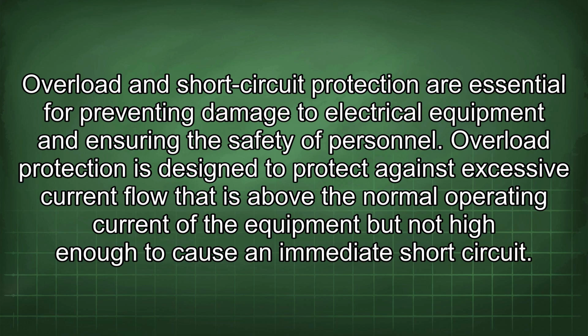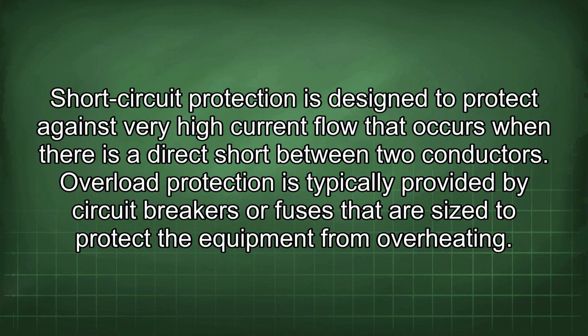Overload protection is designed to protect against excessive current flow that is above the normal operating current of the equipment, but not high enough to cause an immediate short circuit. Short-circuit protection is designed to protect against very high current flow that occurs when there is a direct short between two conductors.